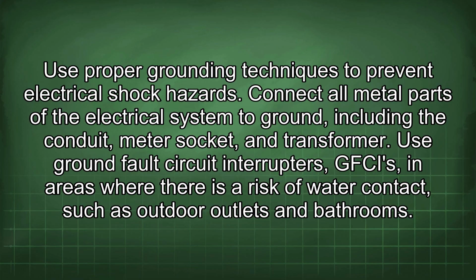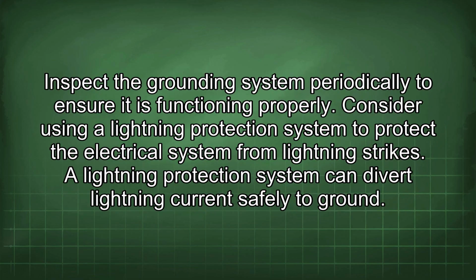Use ground fault circuit interrupters, GFCIs, in areas where there is a risk of water contact, such as outdoor outlets and bathrooms. Inspect the grounding system periodically to ensure it is functioning properly. Consider using a lightning protection system to protect the electrical system from lightning strikes. A lightning protection system can divert lightning current safely to ground.